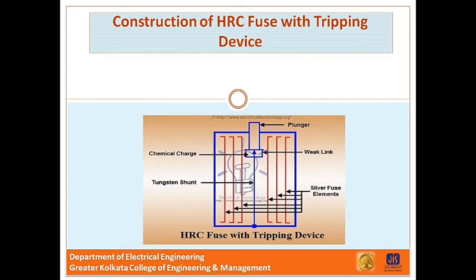Okay. Next one is the construction of HRC fuse with tripping device. Now you can see the essential parts of a HRC fuse with a tripping device. The body of the fuse is of ceramic material with a metallic cap rigidly fixed at each end. Now these are connected by a number of fuse elements. At one end, a plunger which under fault current hits the tripping mechanism of the circuit breaker and causes it to operate. The plunger is electrically connected through a fusible link, chemical charge and a tungsten wire to the other end of the cap.